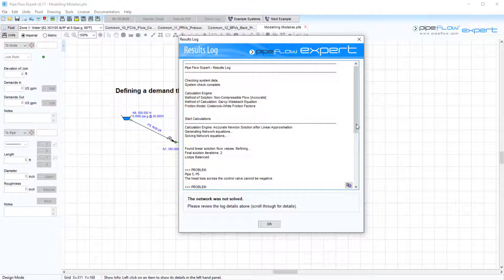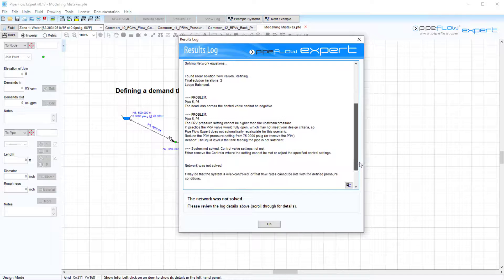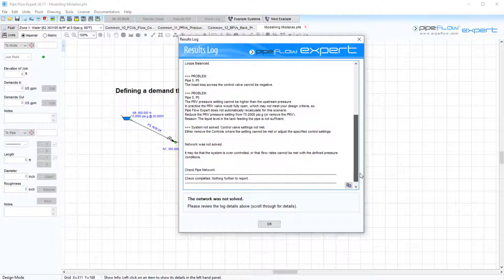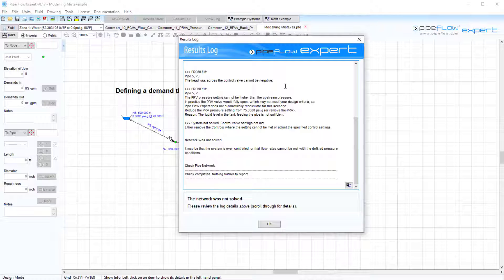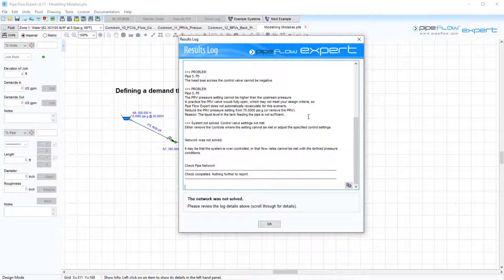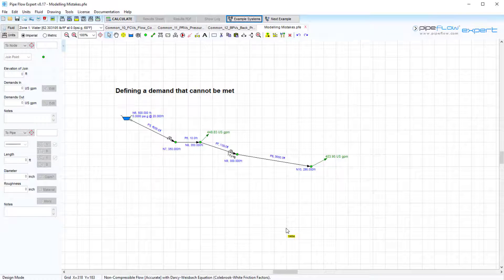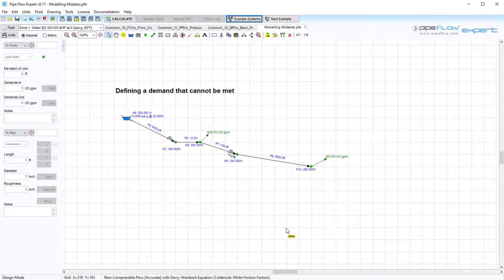As we saw, all three types of valves work by essentially introducing a pressure loss to achieve the desired flow or pressure requirement. Set control valves cannot introduce a negative pressure loss or add pressure like a pump would. If when trying to calculate your system it was found the valve would need to add pressure, it would not be possible to identify a valid solution. The control valve setting will have to be amended, or the flow control valve may have to be removed entirely to allow the solution to be calculated.